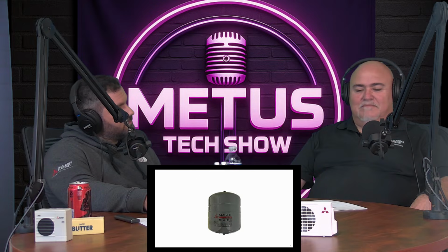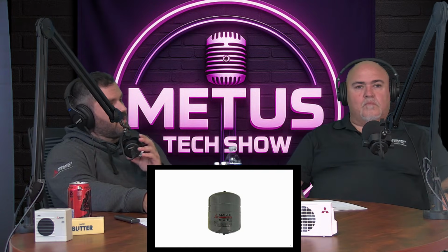But on the other hand, if we didn't have an expansion tank, our relief valves would make quite a mess. Yeah. So relief valves, that's what they're there for. They're there to relieve pressure, and relief valves can only open up so many times, and they're going to end up leaking. Yes. So we don't want that. So again, the expansion tank is really important. Yeah. Absolutely. They've got to account for that thermal expansion. They're a big failure point. They're something that fails pretty frequently compared to other components in the system.